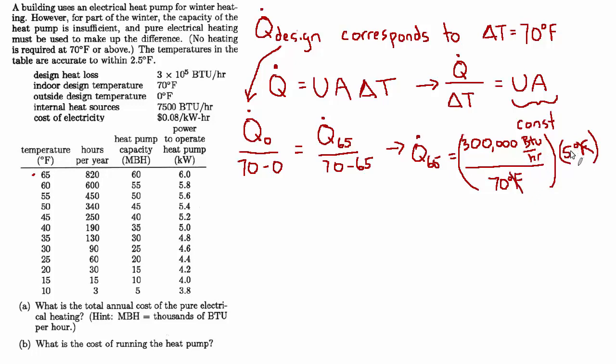And so we can say that the heat loss, the heat that we have to replace with our heating system, is a direct function of the delta T. And we can set up a proportion between different heat losses and different delta T's and set them all equal to each other. So let's apply that by way of our first line in this chart. We can say q_0, meaning the heat loss when the temperature is zero outside, so that's q_design, divided by the delta T, when the temperature is zero outside, which is 70 minus zero.